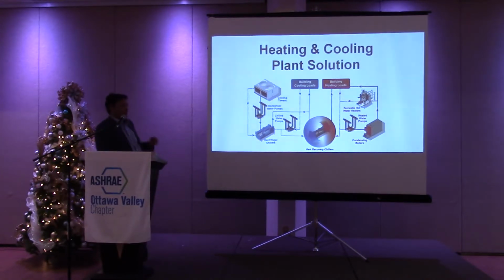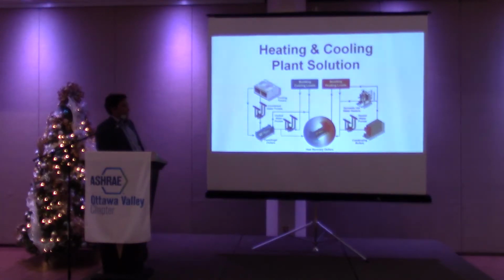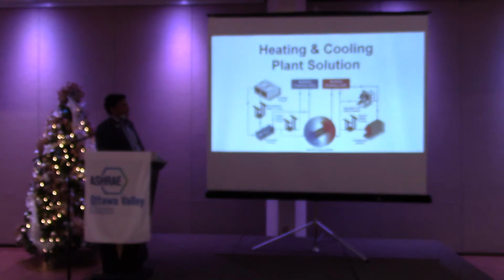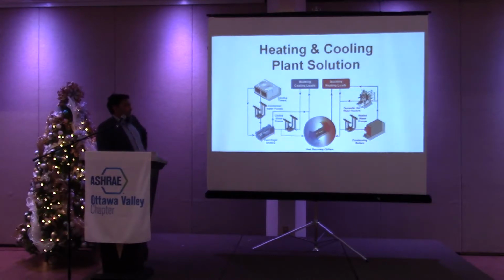We boost just a local loop for domestic hot water up to 160 degrees Fahrenheit to be able to deal with Legionella and those requirements, but the rest of the building was all running at 130 degrees Fahrenheit. So the coils in the building had to be a little bit bigger, but we found that there was definitely a payback in the efficiency.